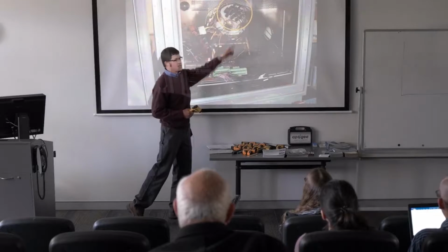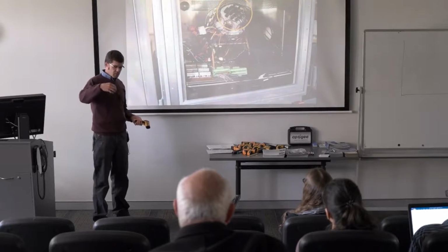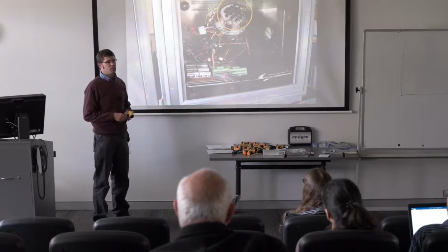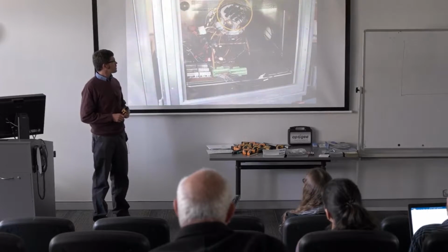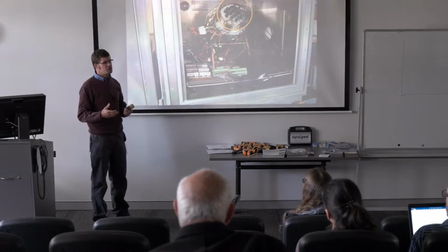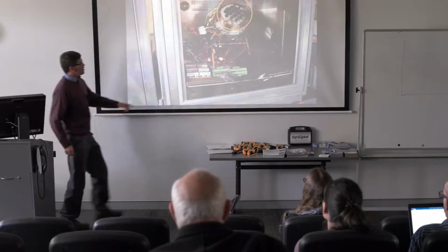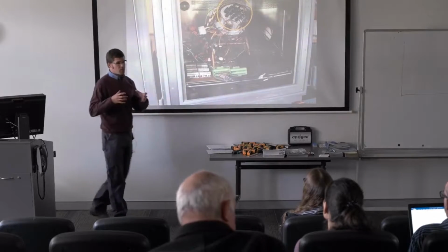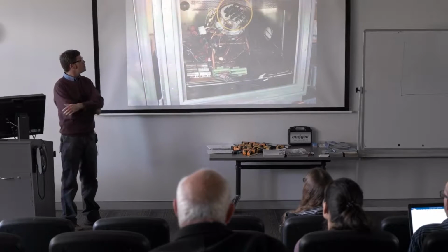There's this cap piece that sits on top of a large piece of aluminum. A piece of aluminum has a big hole in it shaped like a cone, and that's painted flat black. We use that as the black body radiation source that we can fine-tune the temperatures and get specific values of temperature independent of the sensor temperatures themselves.